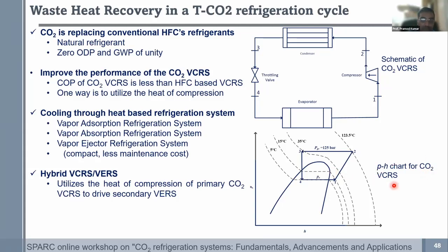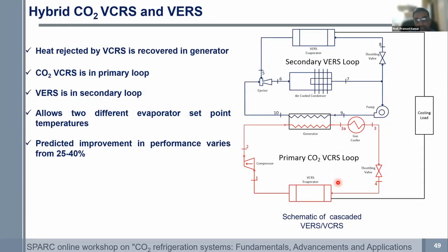The potential problem is that we don't have a suitable oil that goes beyond 165 degrees Celsius. Also, the insulation in the compressors permits you to only go up to about 150 degrees C as the discharge temperature. But once we move towards higher than class H insulation in the motors, or move away from the suction gas cooled compressors, then we'll be able to go to much higher temperatures with carbon dioxide based heat pumps.